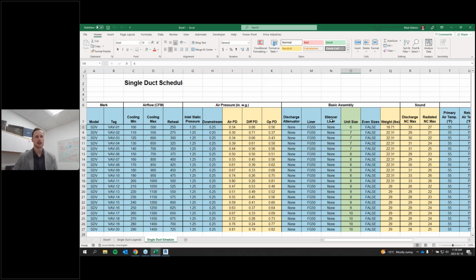There's another demo I can do, which is more of an office building, where we would look at perimeter offices and internal offices, those internal offices having very low loads. We can actually couple three or four of those into a single zone and provide one single duct for them instead. In that auto zoning tool, that's something you can prescribe. What's the maximum amount of spaces you want combined into a zone? What's the maximum amount of zones you want for a single space? That's all stuff you can play with and determine upstream. So great question, Allison. Happy to address that later.